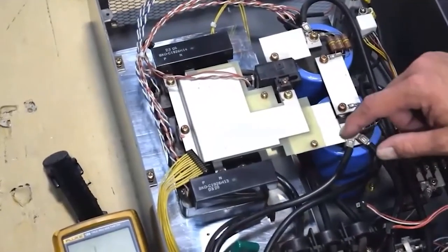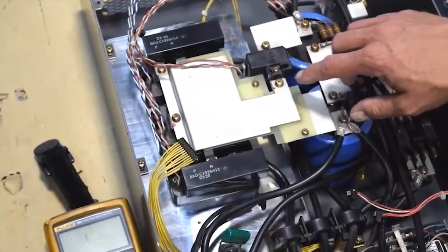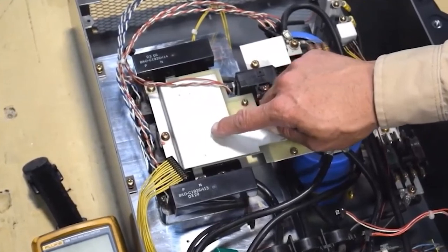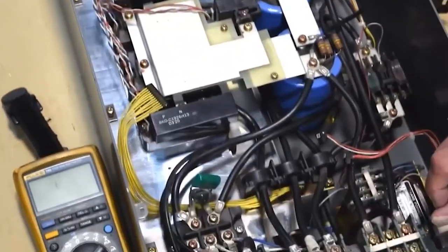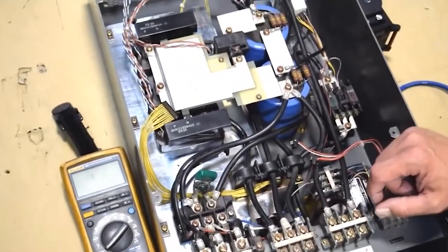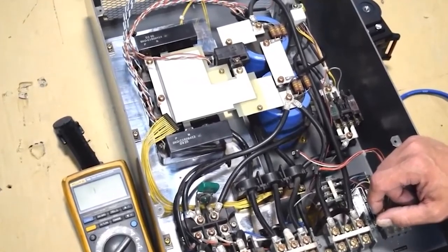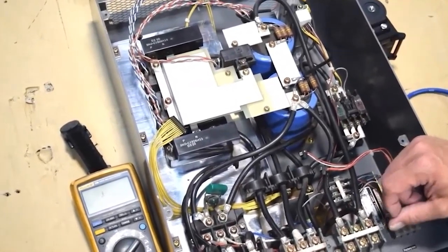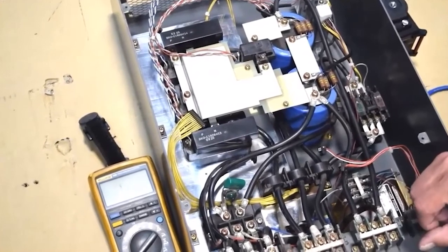Then the next section is the inverter section. This is where your transistors are. This is the section that's going to take your DC and change it back to AC again to run your motor. By doing this, it can control your voltage and frequency at the same time.